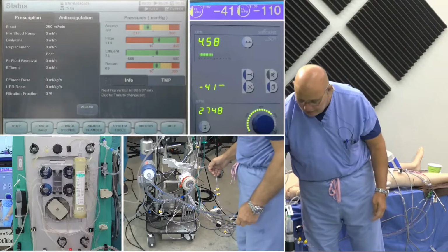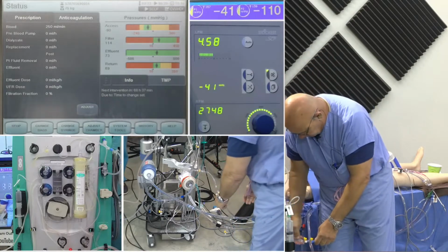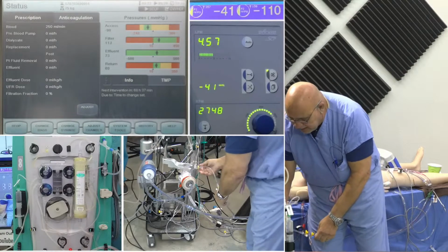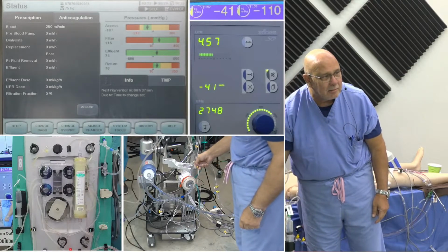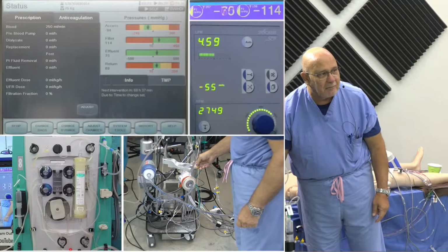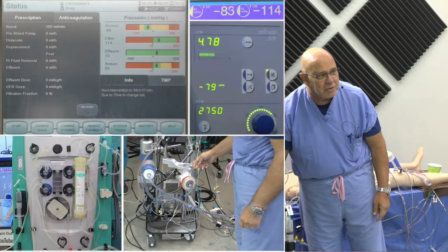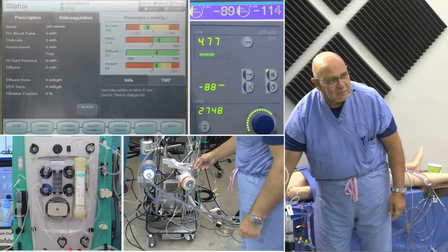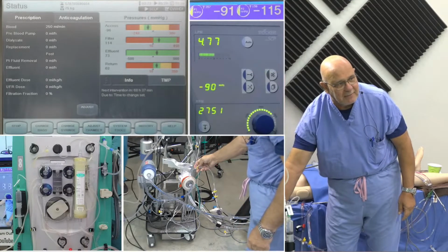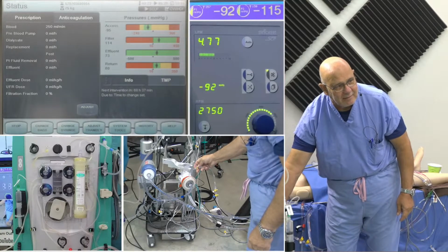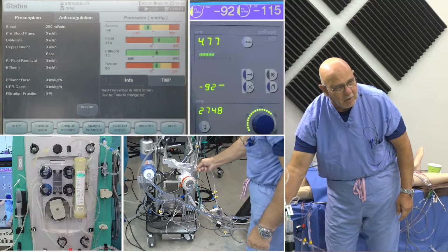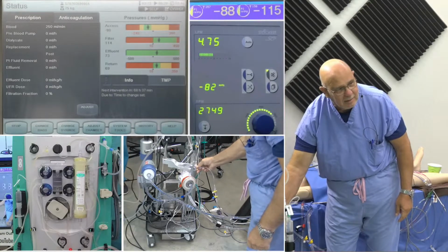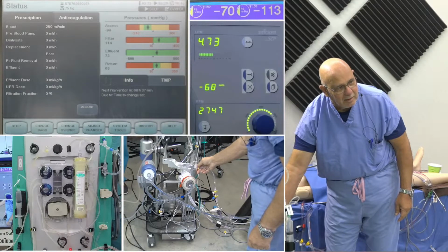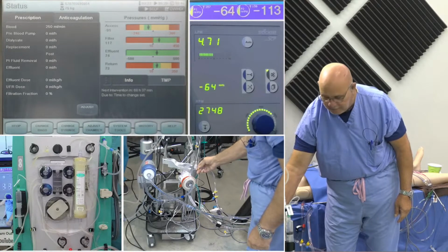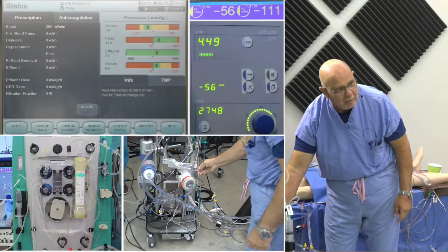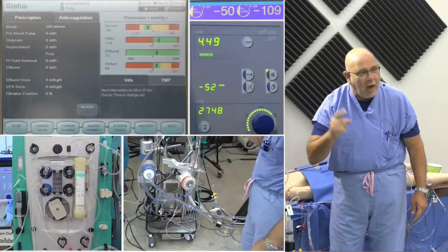When I open that up, so if I close this, look at what my pressures and my flows do. So flow is 4.7, 4.77. When I open it, the flow will go back down, or should go back down to 4.5 if I open the stopcock all the way. There it goes. Now, why is that?